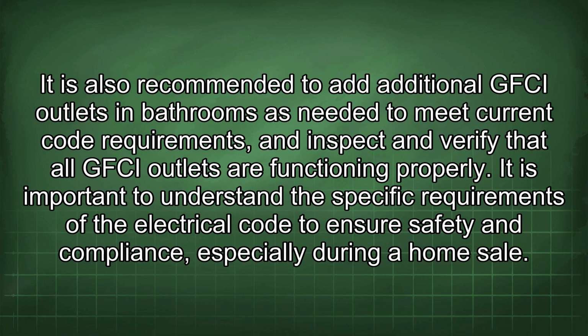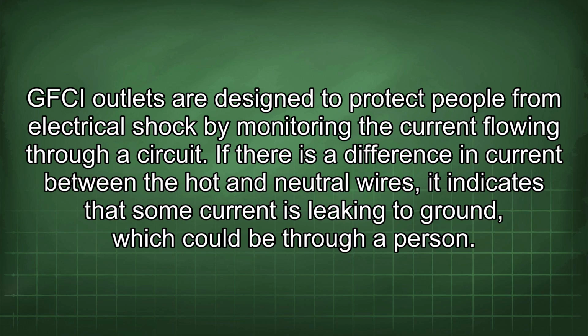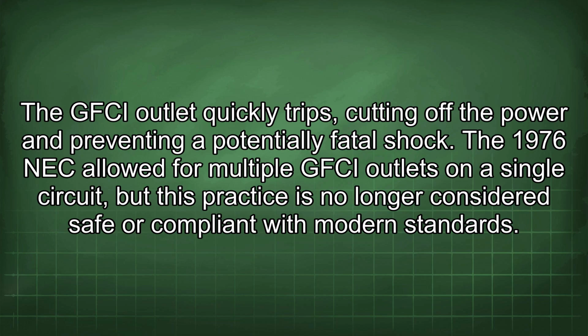home sale. GFCI outlets are designed to protect people from electrical shock by monitoring the current flowing through a circuit. If there is a difference in current between the hot and neutral wires, it indicates that some current is leaking to ground, which could be through a person. The GFCI outlet quickly trips, cutting off the power and preventing a potentially fatal shock. The 1976 NEC allowed for multiple GFCI outlets on a single circuit, but this practice is no longer considered safe or compliant with modern standards.